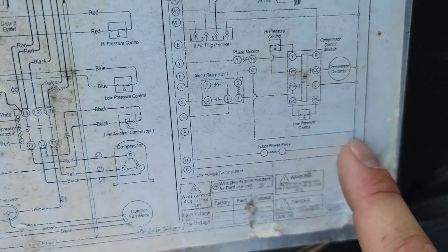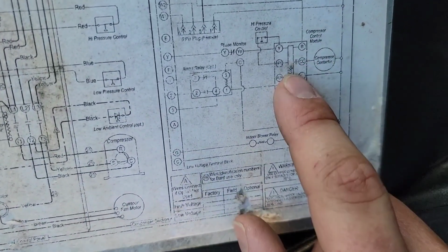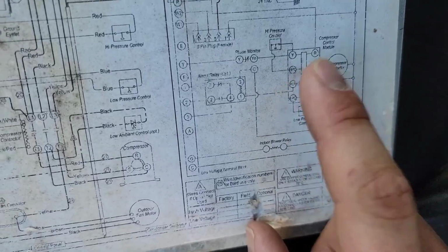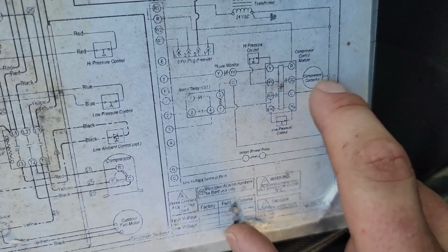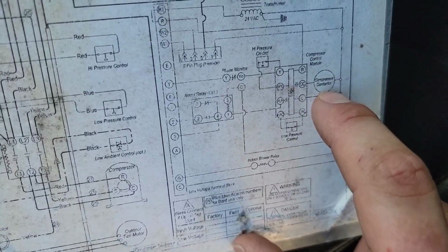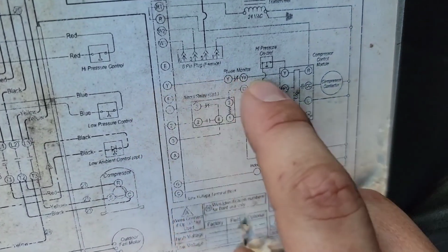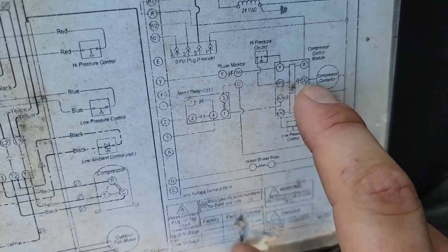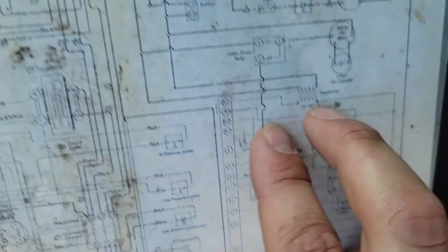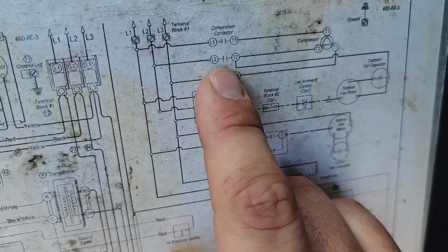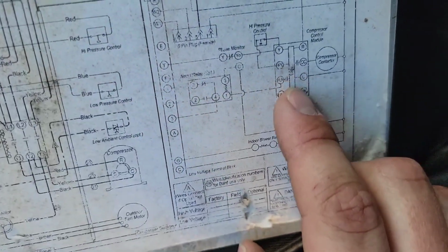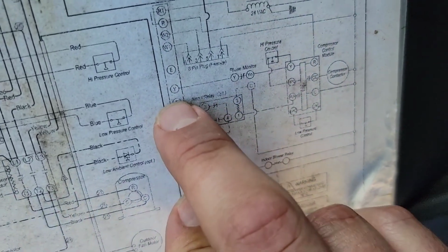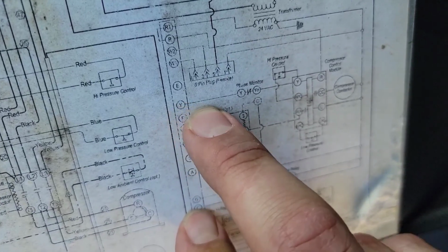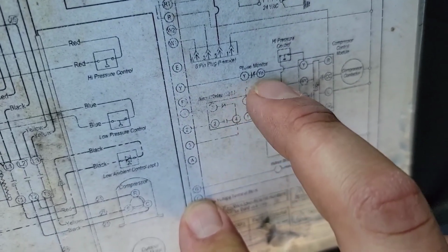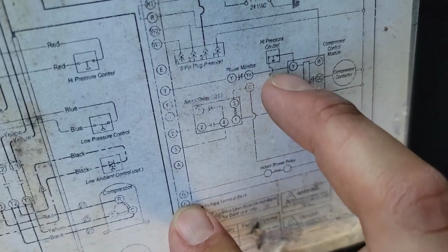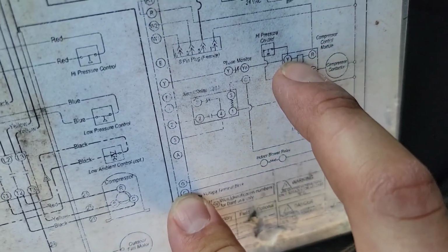Now, that C goes to the time delay relay control right here, low pressure control, high pressure control, and then it goes to one side of the compressor contactor coil. So all we need is the Y to connect to the other side, and then that coil will energize and it'll close these contacts, therefore sending power to the compressor. Now let's go back here. If we measure from C to Y, we should have 24 volts. Then we go to the phase monitor, and then from the phase monitor, see it says Y out, to this Y, which is the time delay relay control.